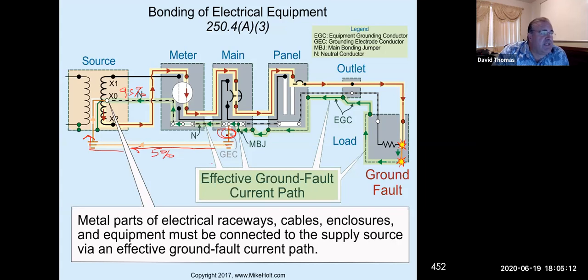So what I typically do when I get into my panels is I have a clamp-on meter, and I'll clamp it on the neutral and I'll clamp it on the ground, and I should see 0 amps on the ground. If I see anything on there, I've got something wrong. But it could also be induced current, so I'm expecting to see a little bit of current flowing, but not a large amount. If I do have that happen, it's because I've got a problem in my electrical system. Somebody wired up the most ridiculous things. There are so many systems out there that have these dangerous conditions, and they've been like that for a long time. Fortunately, nobody gets killed, until you come in there and find this.